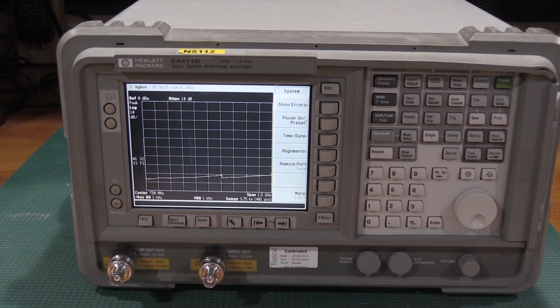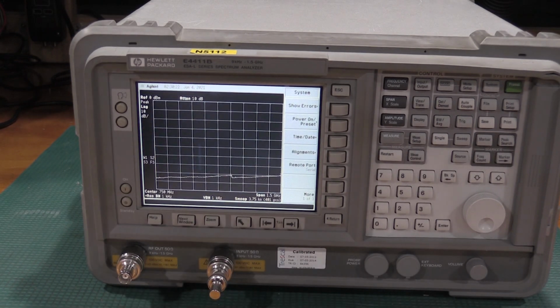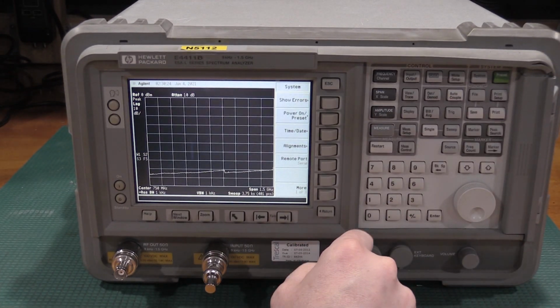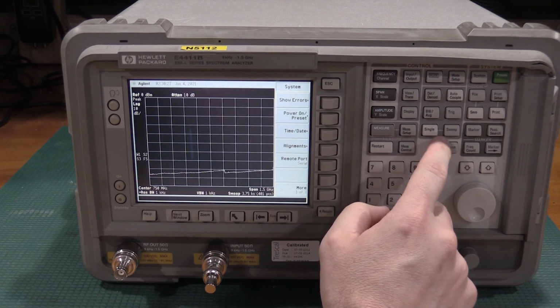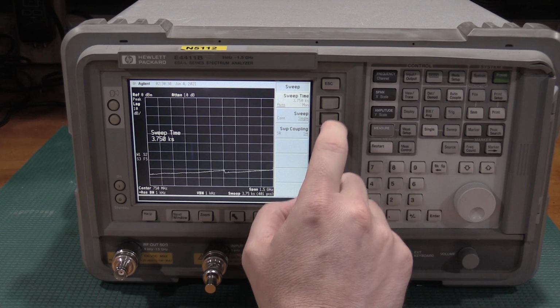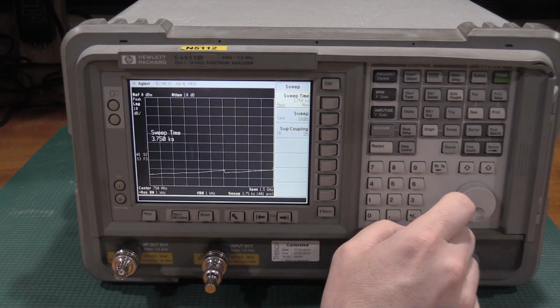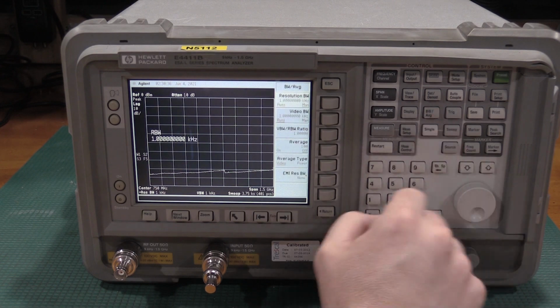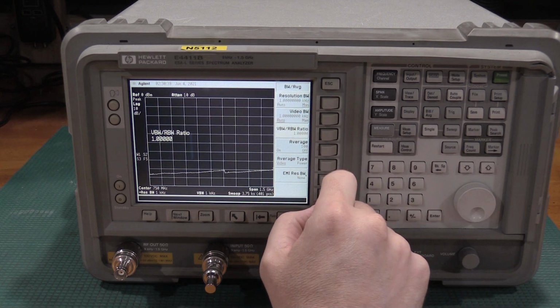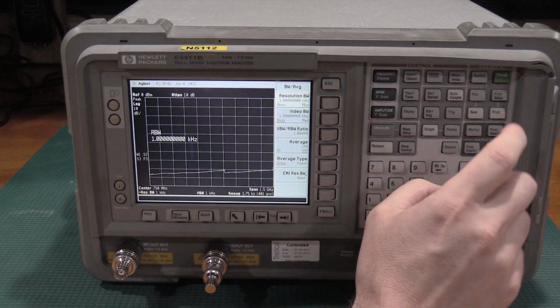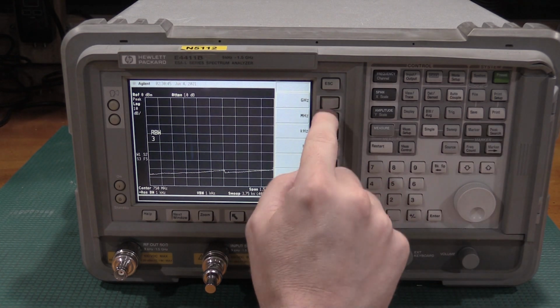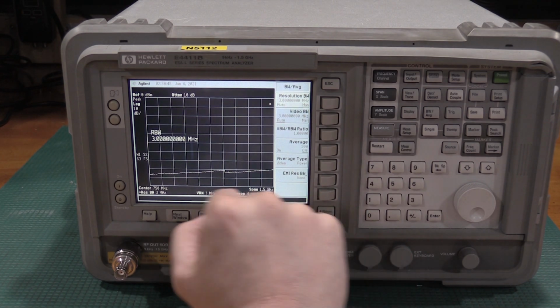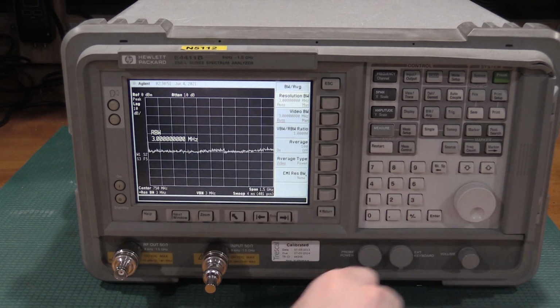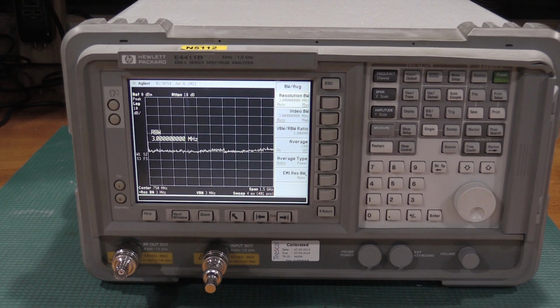So what we'll do, to make sure it works, is put the terminator on it, and let's see, sweep. Let's see, bandwidth. Yeah, video and resolution should be the same. Resolution bandwidth will go to 3 megahertz. Our sweep time is now 4 milliseconds, so let's fire off a sweep. And there's our sweep. It's more noisy because it was faster.